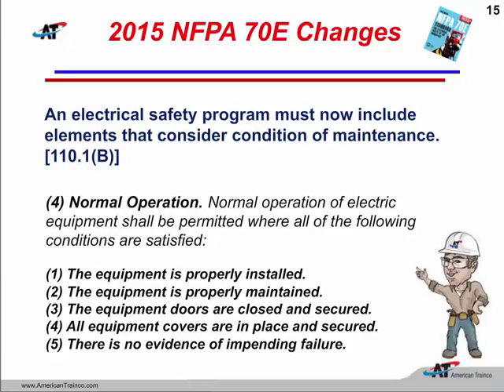And you know, so that's going to be another example I might be able to give you on this. Normal operation of electrical equipment. A single pole switch, wherever we work. Well, we walk up, really, there's no real maintenance of that single pole switch. I mean, we might take a visual look at it, and if it's intact and nothing broken, the handle's still there, we're going to operate that with no PPE on. Okay, so that's normal operation. Well, I get to, let's say, injection molding equipment, and I'm going to operate the circuit breaker that controls that equipment. Well, that circuit breaker probably has not been exercised every year. Maybe it has not been megged out. Maybe it wasn't torqued correctly over the years. So proper normal operation is not going to happen on that. We would have to put the PPE on that involves that piece of equipment and make sure that we operate it with some protection on us.